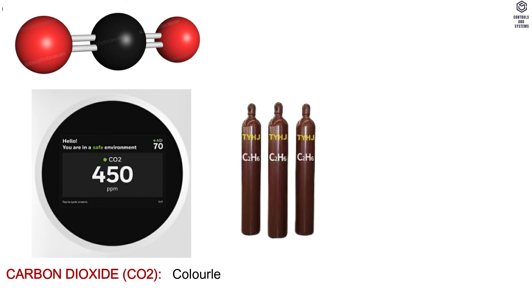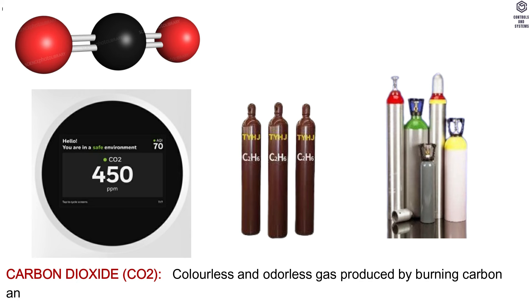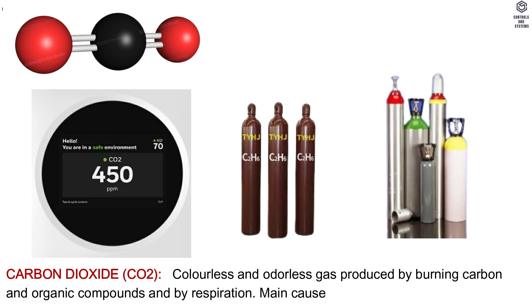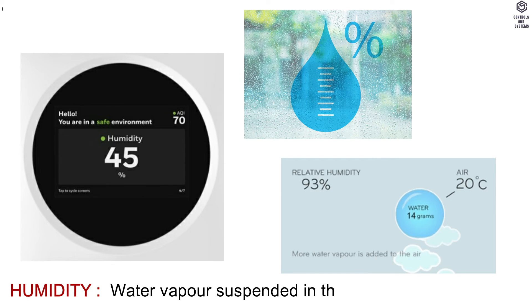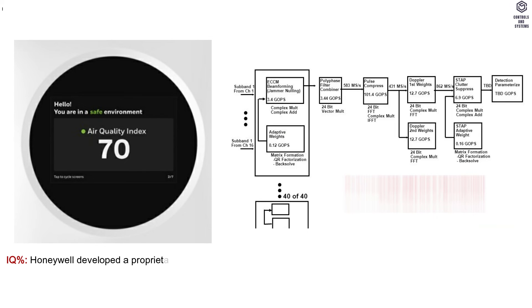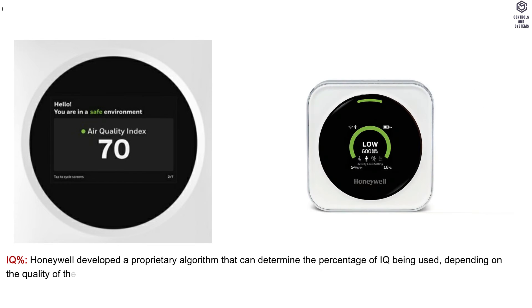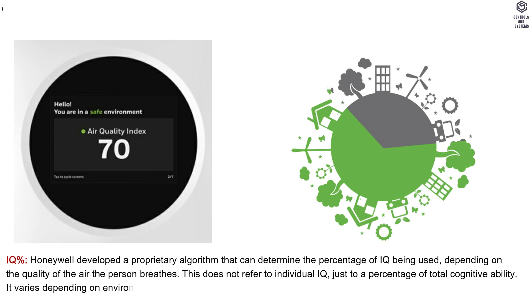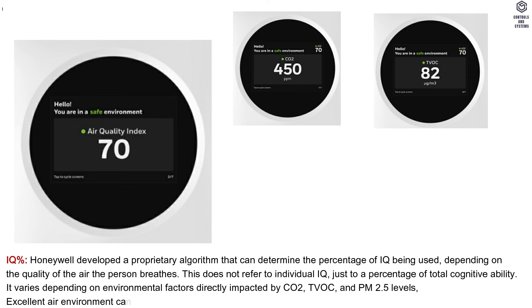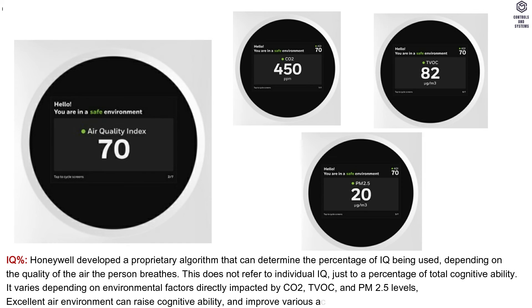Carbon dioxide (CO2): a colorless and odorless gas produced by burning carbon and organic compounds and by respiration. The main cause of buildup is poor ventilation. Humidity: water vapor suspended in the air. IQ%: Honeywell developed a proprietary algorithm that can determine the percentage of cognitive ability being used depending on the quality of the air a person breathes. This does not refer to individual IQ, just to a percentage of total cognitive ability. It varies depending on environmental factors directly impacted by CO2, TVOC, and PM2.5 levels. An excellent air environment can raise cognitive ability and improve various activities.